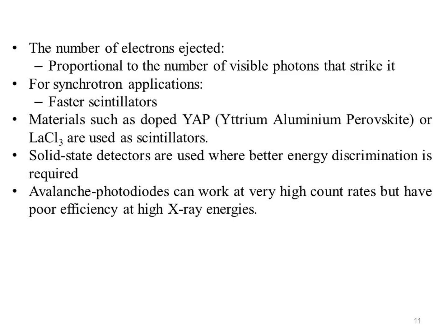Solid state detectors based on silicon or germanium are used where better energy discrimination is required, and avalanche photodiodes can work at very high count rates but have poor efficiency at high X-ray energies because silicon does not absorb such photons strongly.